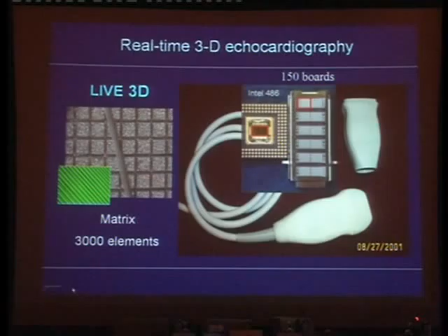These transducers are 100% more effective than the piezo crystal transducers that are used as standard in most of the currently available systems. This is a standard transducer, and this is like packed sand. All these transducers have their vectors in different directions when they are inactivated. When you activate them, they are not squeezing out energy all in the same direction, so you get only 40% effectiveness, whereas these transducers go up to 85%.